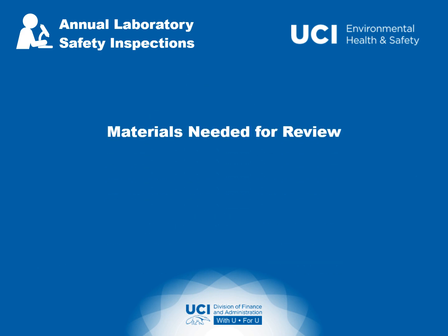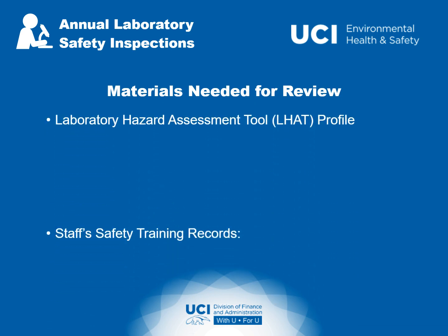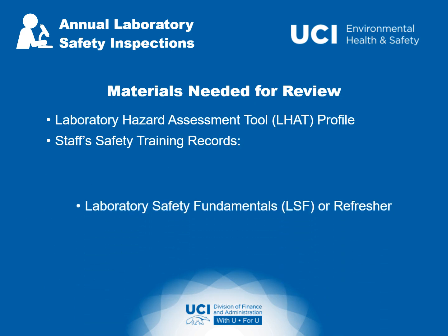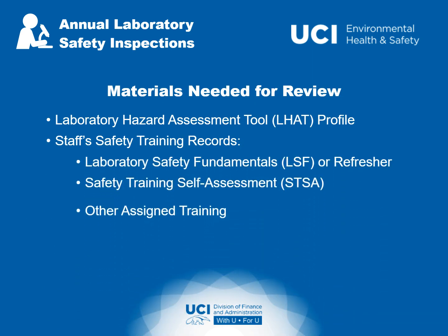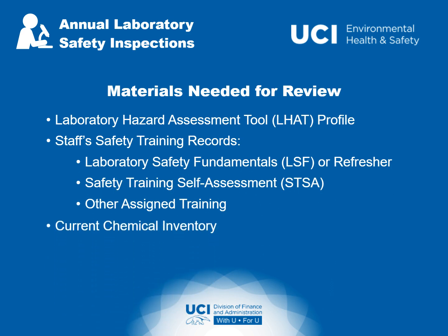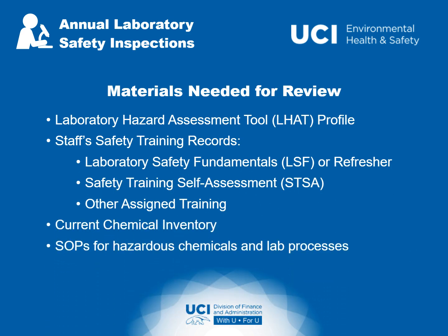Please have these materials ready to review during the inspection: the laboratory hazard assessment tool or LHAT profile, including PPE training, hazard assessment review, and update of staff roster; lab staff's completion of safety training; the lab's current chemical inventory; and standard operating procedures for hazardous chemicals and lab processes.